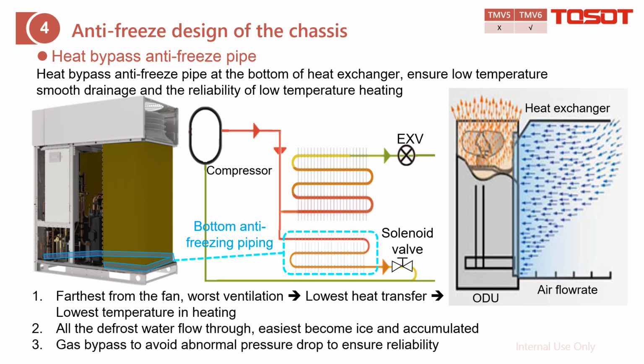So we just sacrifice this one and make it separate from above. And also from here we can get the hot gas bypass, and then we can prevent the ice accumulating at the bottom. On the other hand, as this one just connects the compressor discharge and suction side, it can act as a gas bypass.